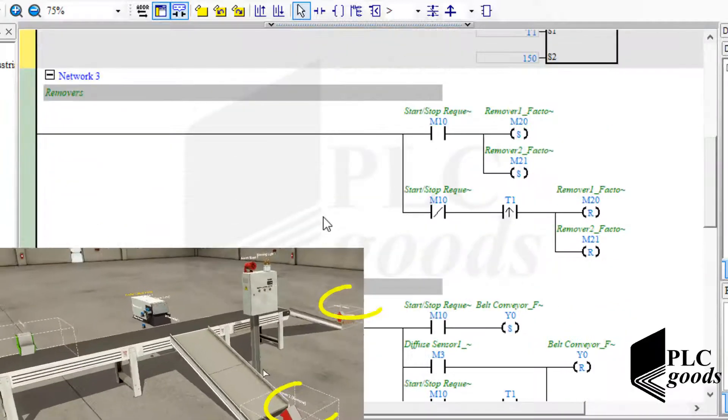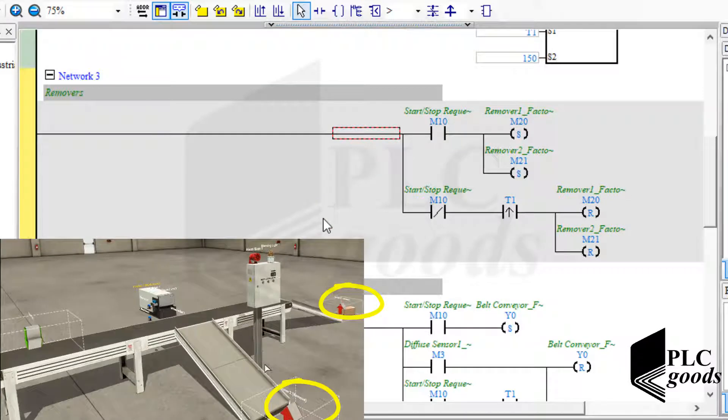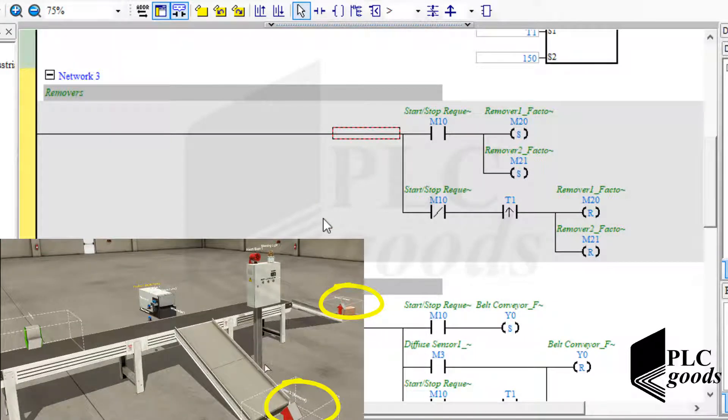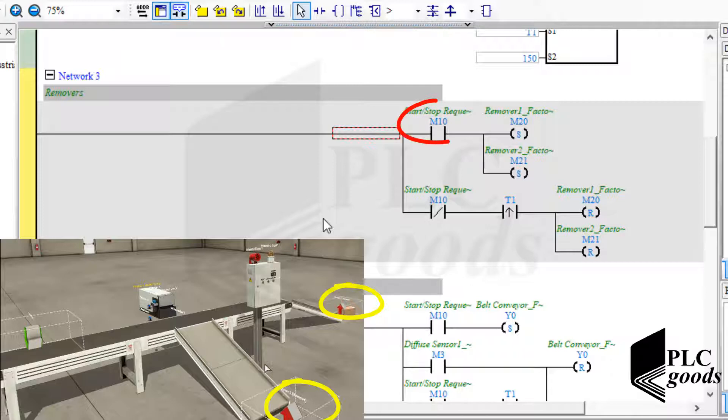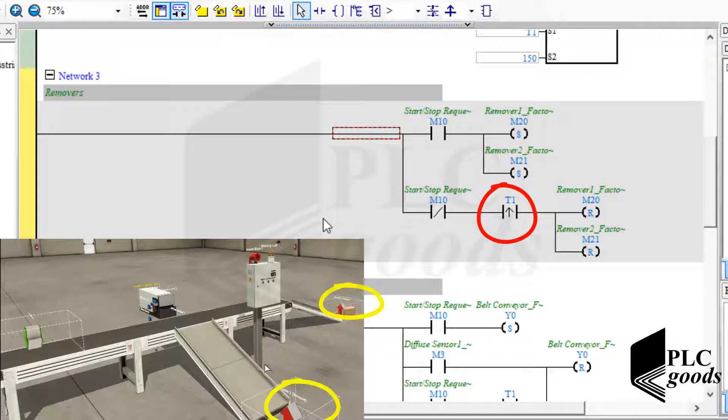The next network is related to removers. If PLC detects a start request, in another word if this bit is one, then PLC will turn on two removers immediately. Otherwise, PLC will turn off two removers after 15 seconds when the second timer reaches to its defined time.